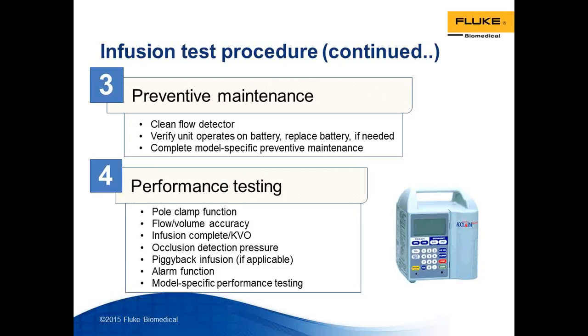This includes volume accuracy, which is the delivered volume to the patient; flow accuracy, which is making sure that the medication is delivered at the right flow rate; and occlusion detection pressure, which means that, as I'm sure all of you are aware, in case there's a blockage, the infusion pump should alarm immediately based on a certain pressure threshold. Then other alarm functions associated with that, as well as pole clamp function. And then, of course, depending upon the infusion pump, whether it's a 1-channel or 2-channel, there might be other things related to performance testing. But when we generally talk about performance testing, testing pressure, flow, and volume are the 3 top-of-mind and most critical parameters.